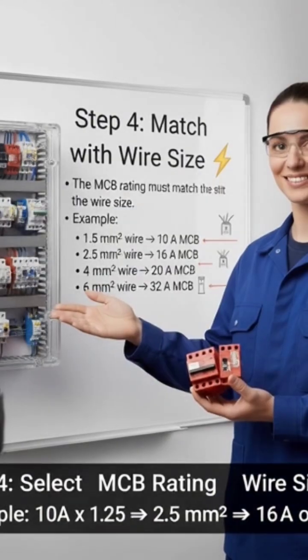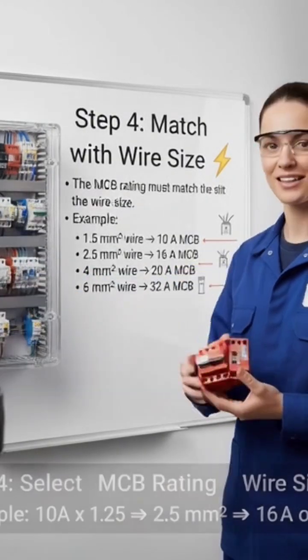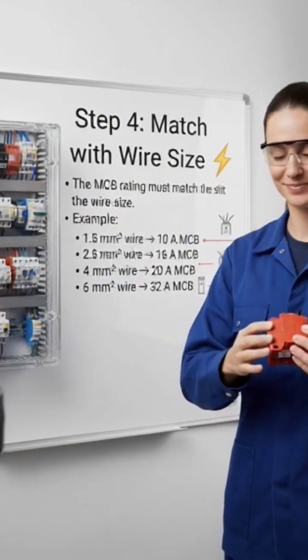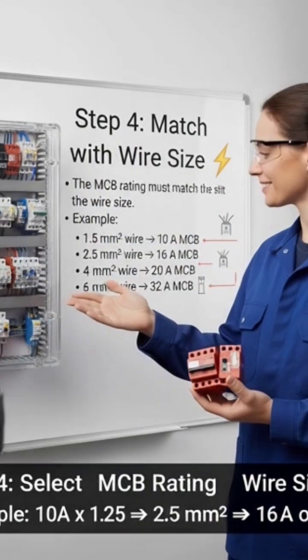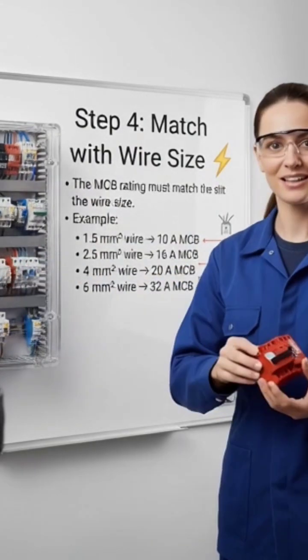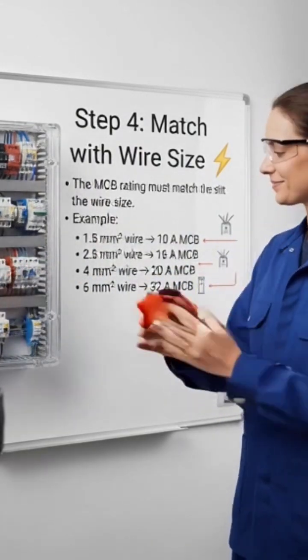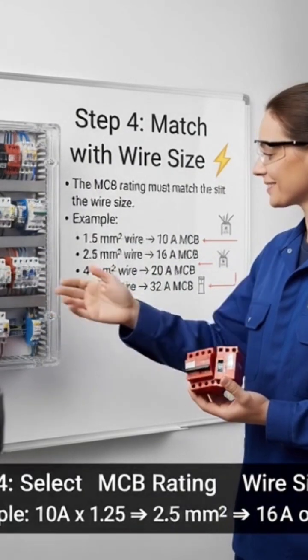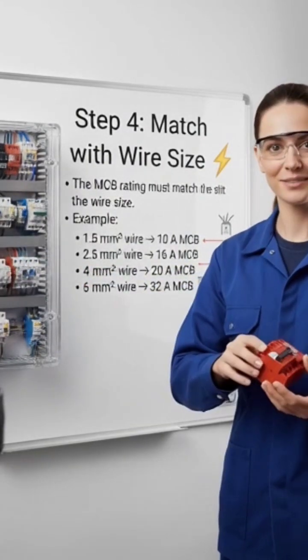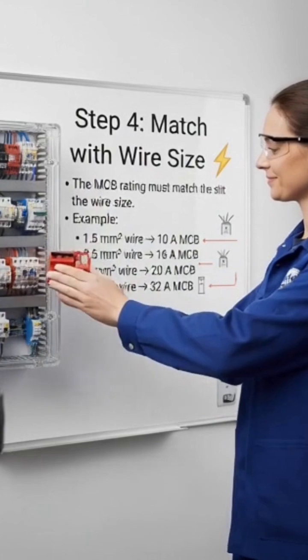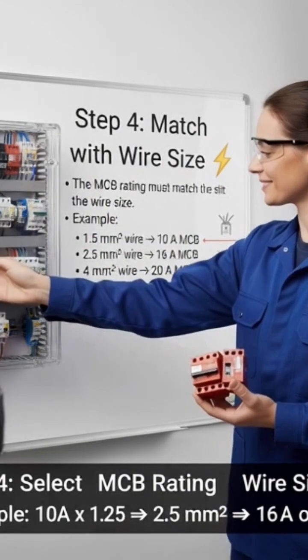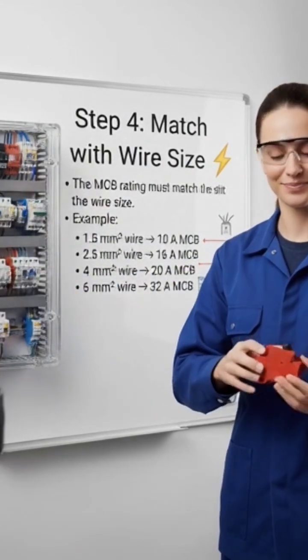Step 4: Match with wire size. The MCB rating must match the wire size. Example: 1.5 mm² wire uses a 10A MCB, 2.5 mm² wire uses a 16A MCB, 4 mm² wire uses a 20A MCB, and 6 mm² wire uses a 32A MCB.